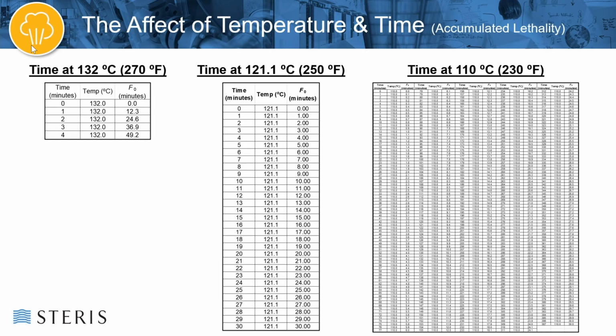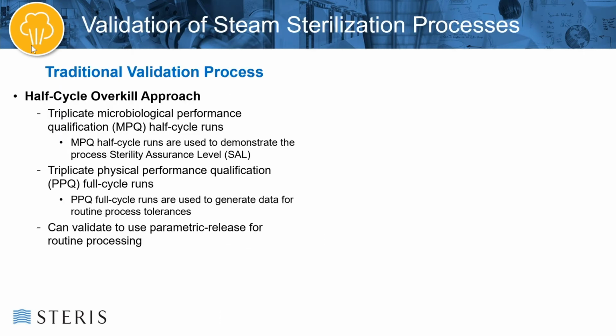Now I want to touch briefly on validation of steam sterilization processes. There is the traditional validation process, which looks very similar to what you would see for an ethylene oxide sterilization process, where you've got a half cycle overkill. You're running 3 consecutive microbiological performance qualification runs, or MPQ runs. These are typically half cycles. There will be BIs in these cycles that will have usually in excess of 1 million organisms for your indicator organism.